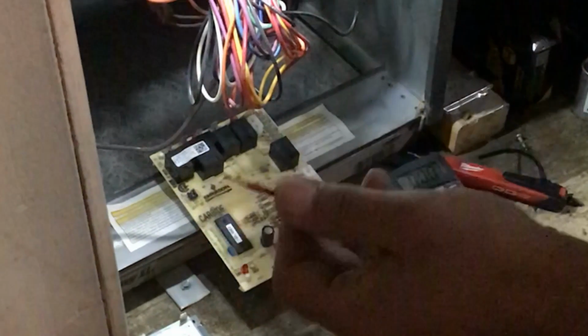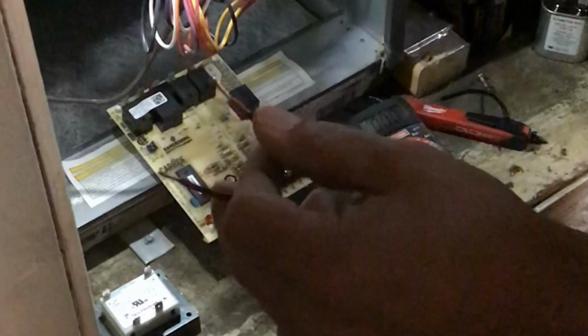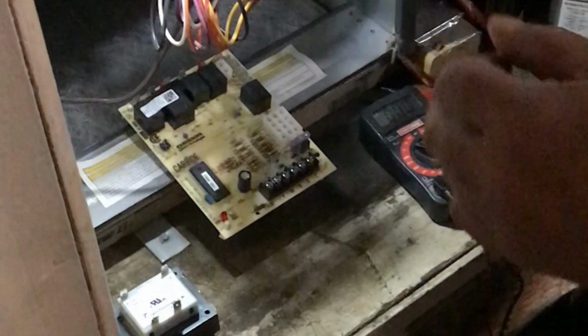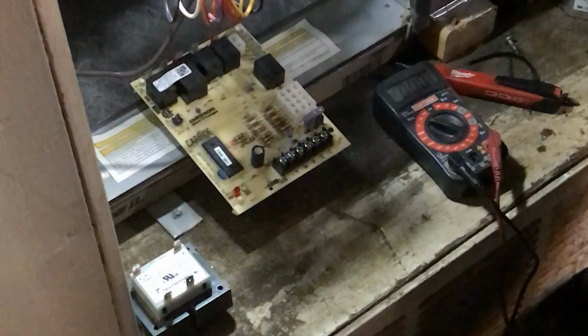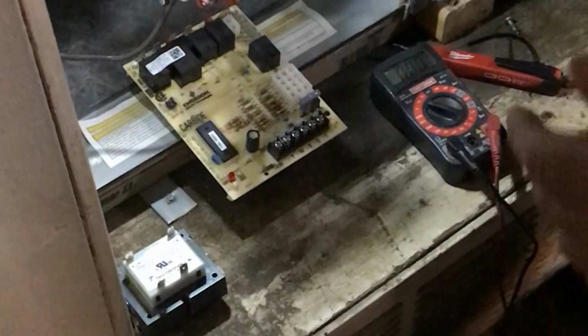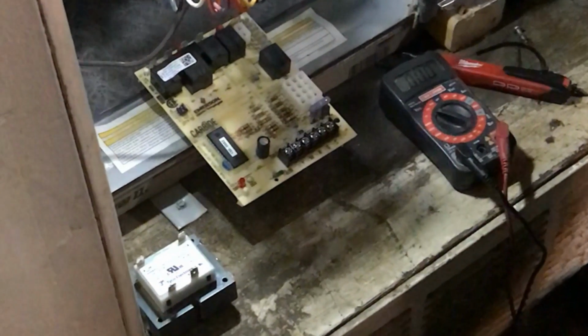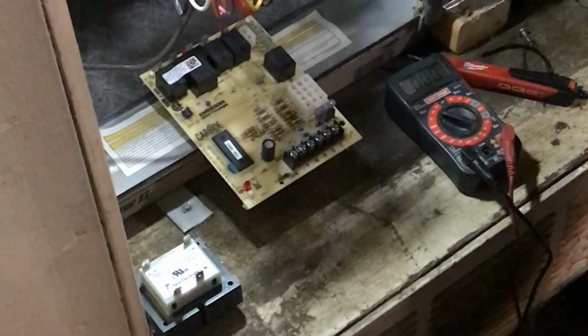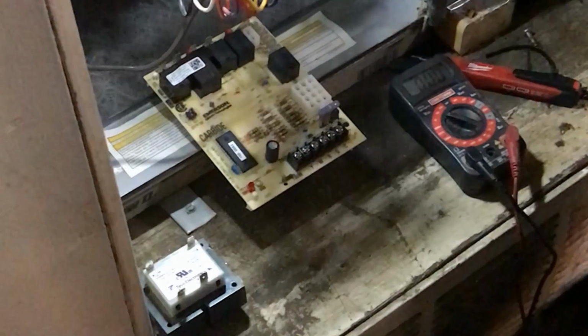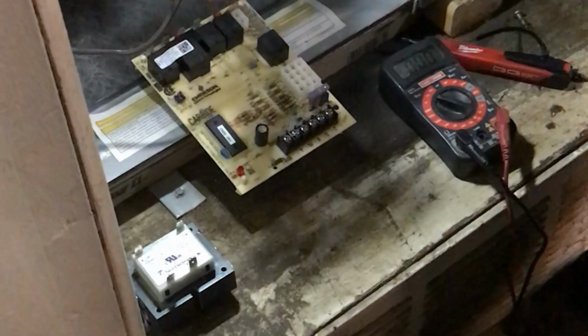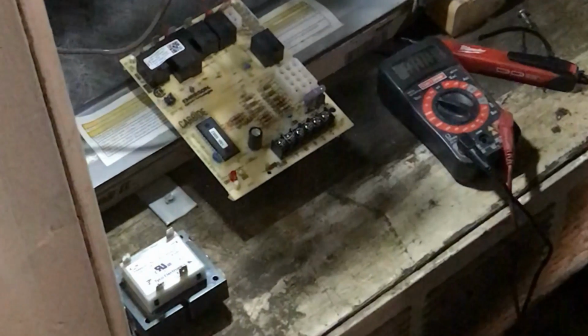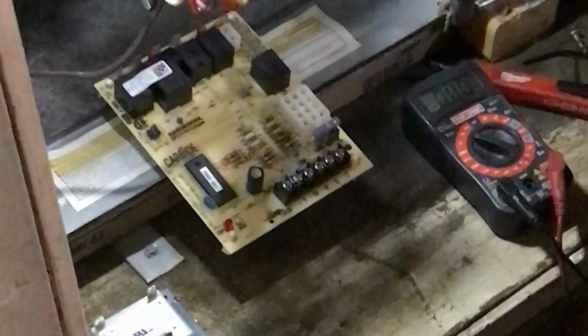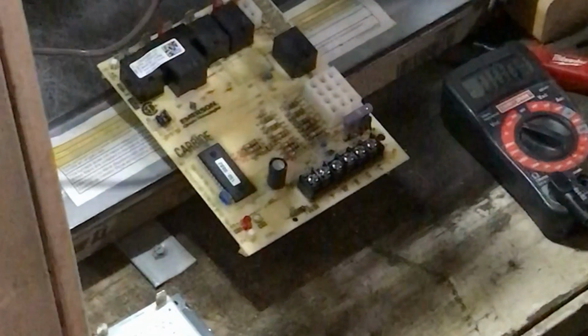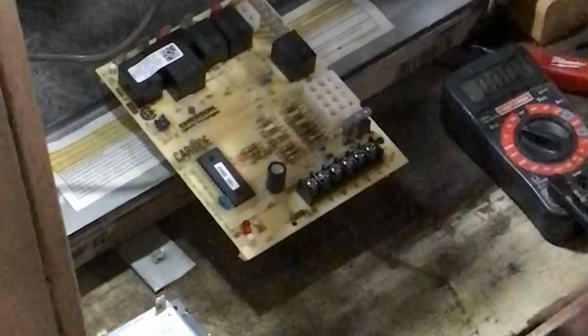Alright, I'm going to talk a little bit more about using the jumper wire. Basically what you're doing when you're jumping from terminal to terminal is you're taking the thermostat out of the equation. So it's a real telltale sign to see if your thermostat's bad. I've seen a lot of people go to the thermostat and take it apart and tie wires together and jump it out at the thermostat. It's easier to just do it right here. So if you're not getting indoor fan operation, your contactor's not getting 24 volts outside, and you're suspecting that the thermostat could be the reason, it can all be troubleshooted right here on these terminals.